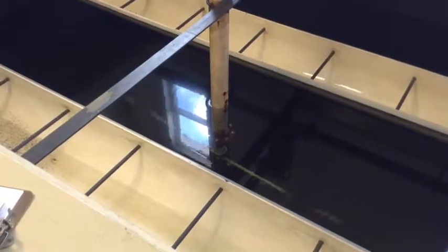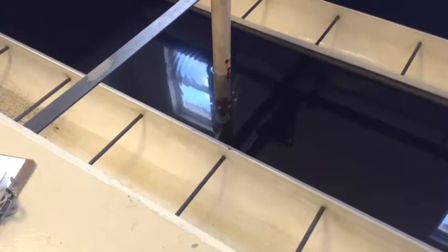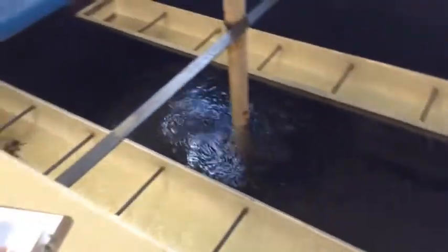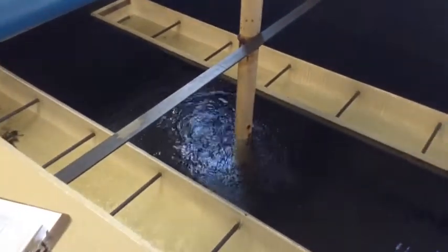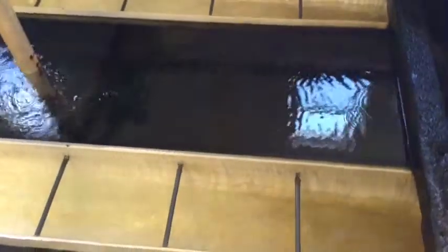It gets it going as the wash water starts, because these are a high rate, mixed media filters. So what happens is they'll take 4 gallons per square foot, but when you backwash it, you've got to run 12 to get the particles to come back out. You can see where it starts out, it's not too bad looking. In a few minutes it'll look like chocolate.